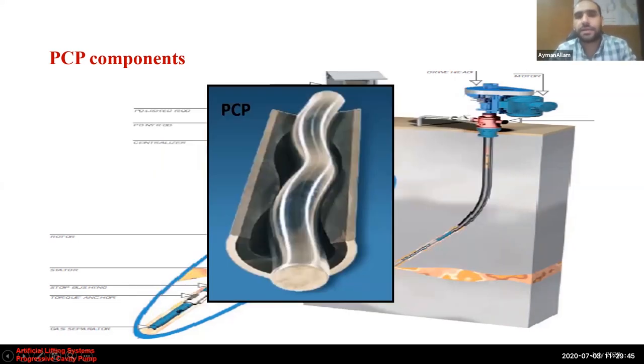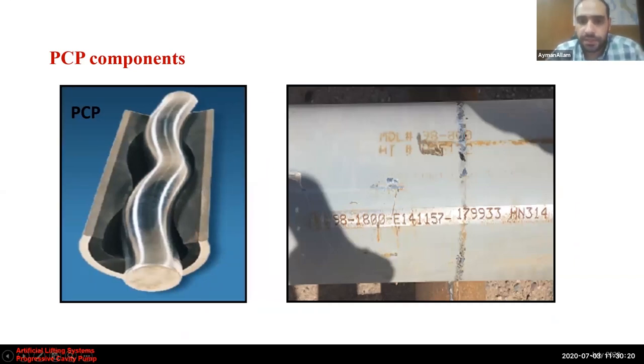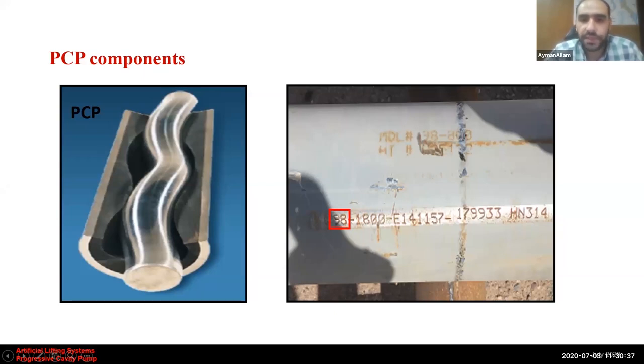The last component and the heart of the system is the downhole pump itself. It simply consists of only two parts: the rotor and the stator. The rotor is a helically machined piece of steel covered with chrome, while the stator consists of a steel tube with an elastomer rubber, bonded together using bonding material. To identify a PCP, check the serial number on the stator. The first two digits — for example, 38 — refer to the pump capacity or displacement, meaning 38 cubic meters per day per 100 RPM.